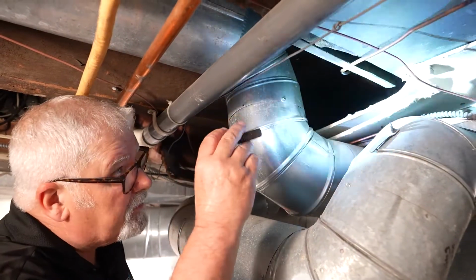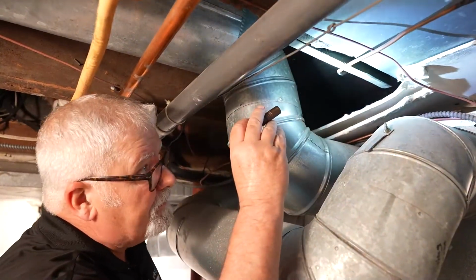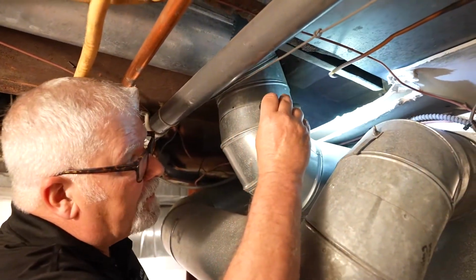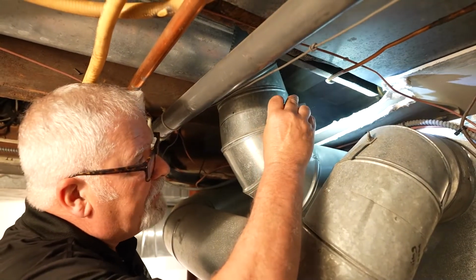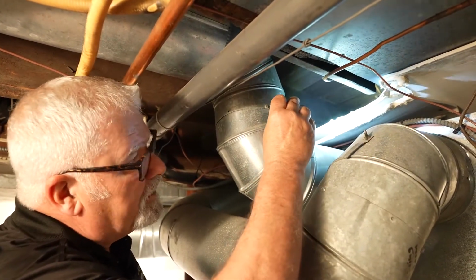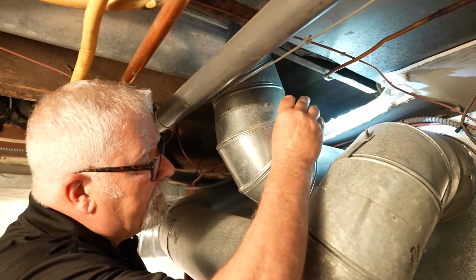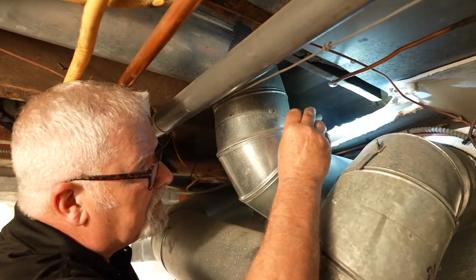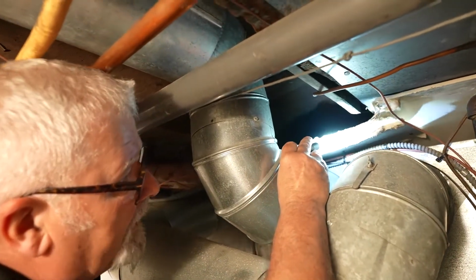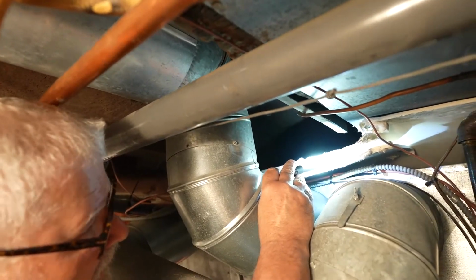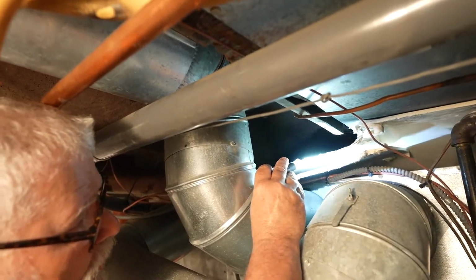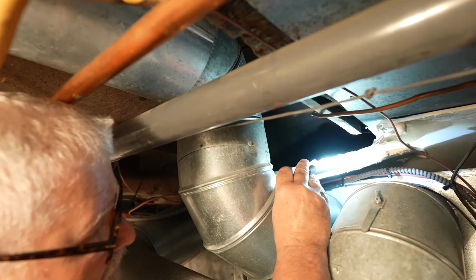During our inspection, when we looked at this panning material, I felt some air coming out with just the furnace running. I looked back up inside here and we've got some supply leakage again, we can fix that. But the big concern is this return - the wood actually looks like it's had some termite damage, so I've got a big hole we'll have to hand fix before we start aerosealing.